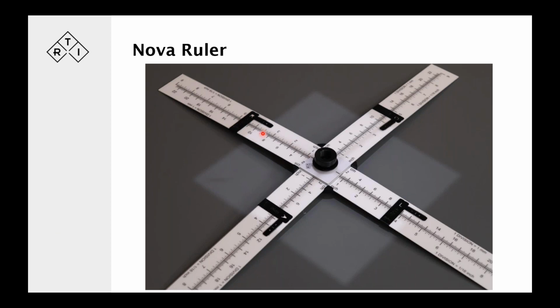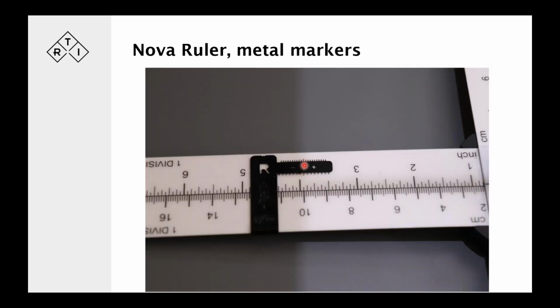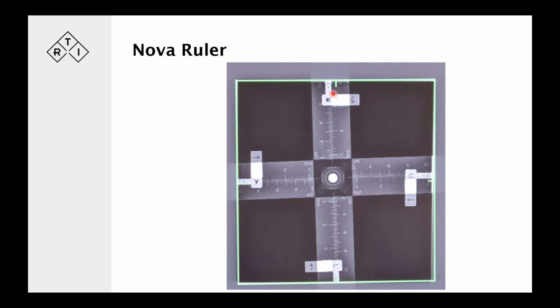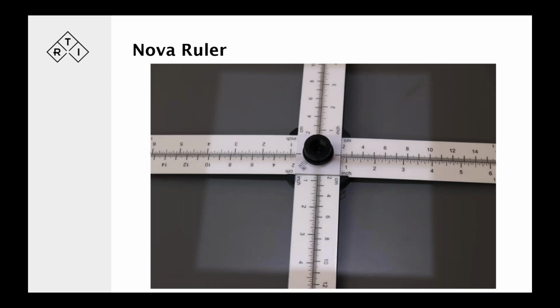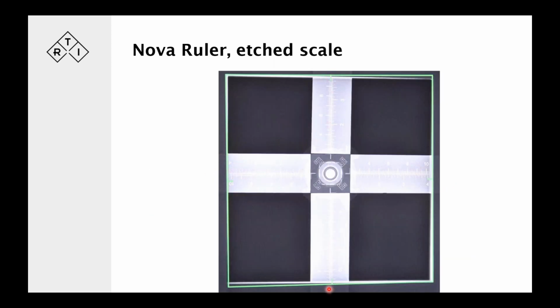Nova Ruler is a device here also that is used to measure the light field and X-ray field correlation. It has markers on it that you can then set to 0, where the light field ends or starts, and make an exposure, and then you can look and see how well that matches the X-ray field. Because of course you'll get that through, they're metal. The clips are metal. You can use it also without those markers. Make a note of where the X-ray field or the light field edge is, and then make an exposure, and there's an etched scale in the ruler, so that you can make a readout and do the comparison afterwards once you view the X-ray image.